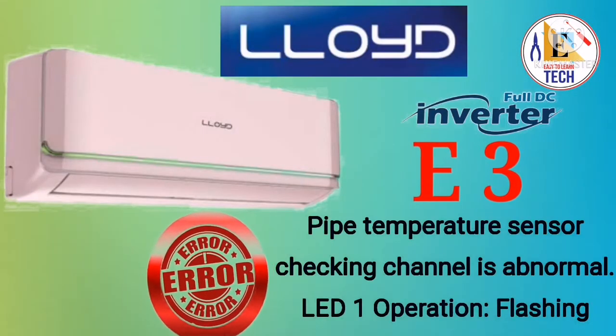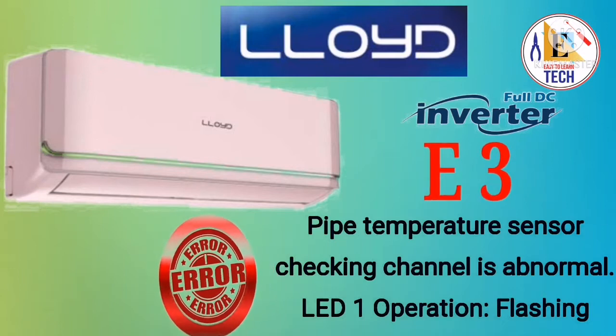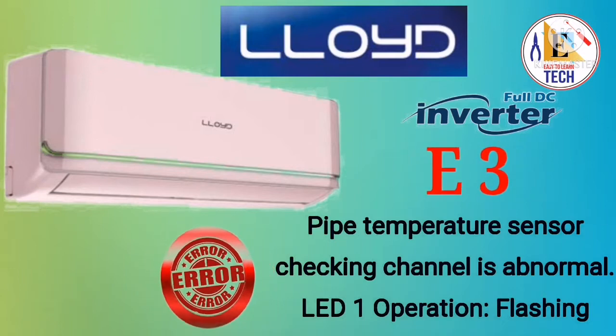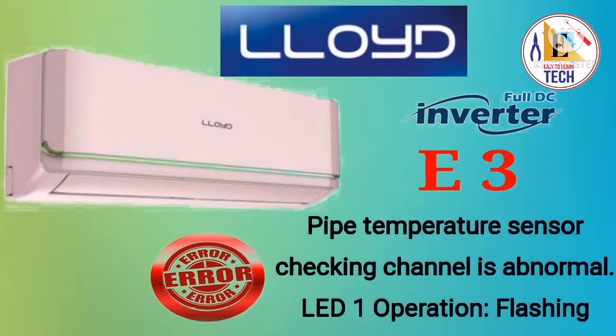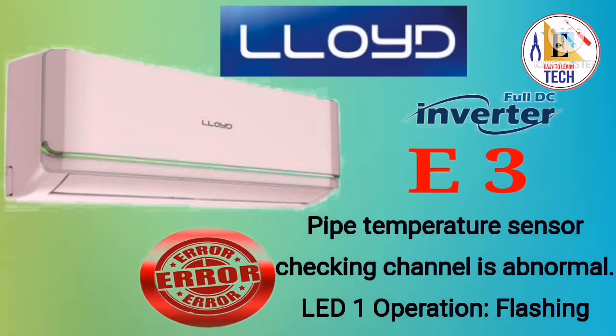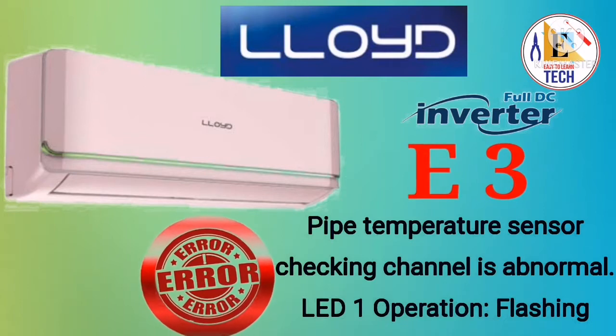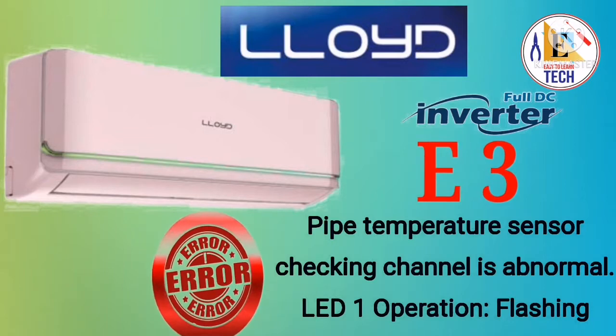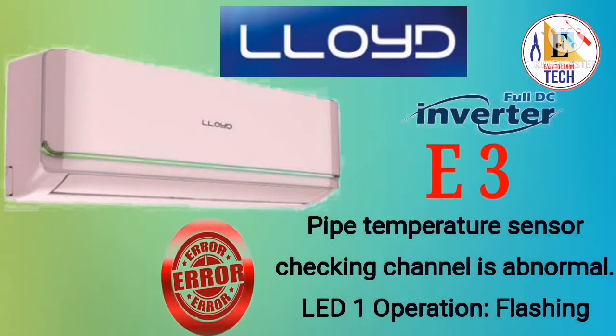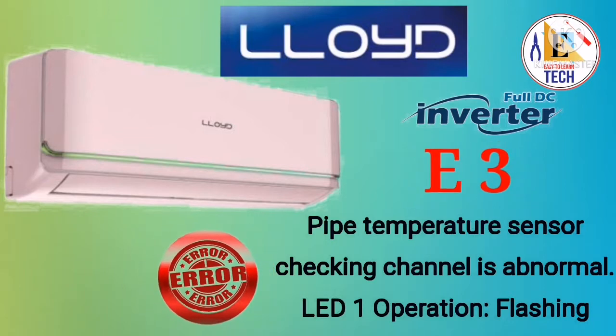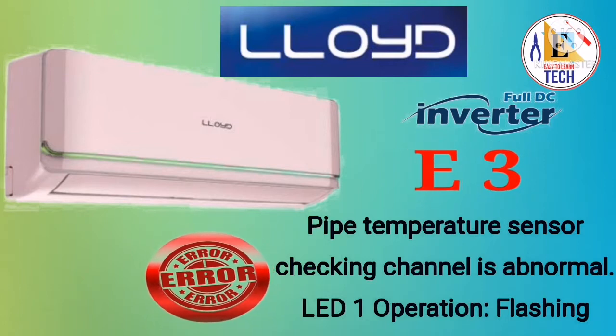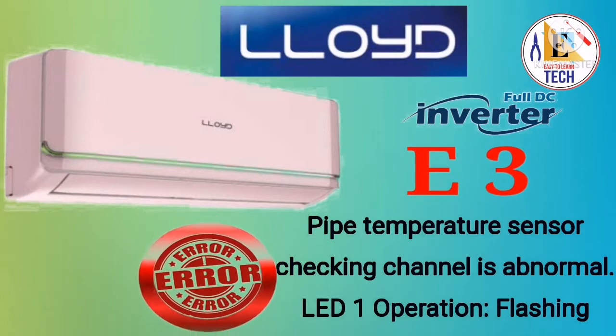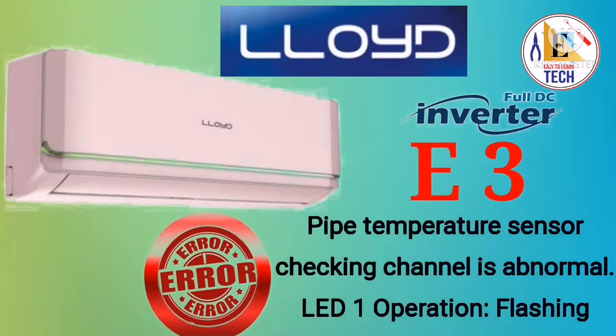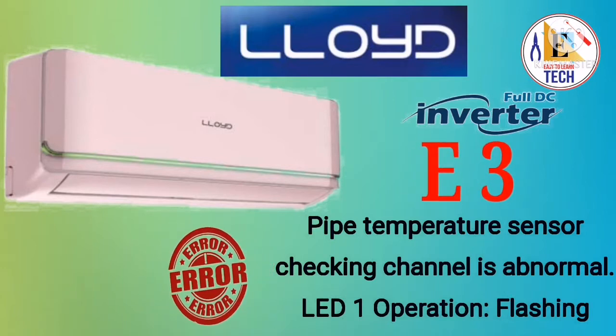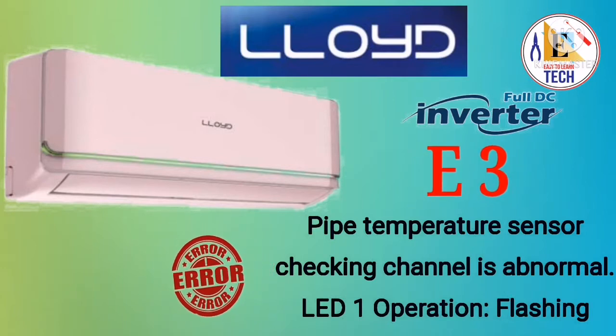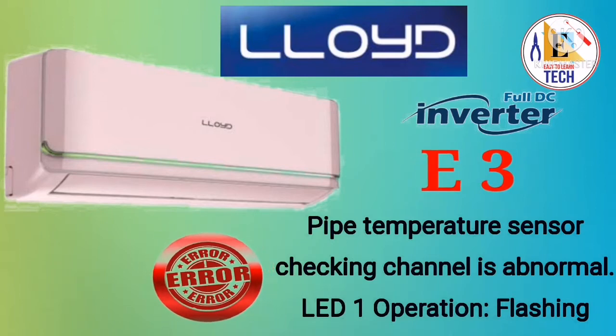When you see E3 in your display, or your LED1 operation is flashing, it means pipe temperature sensor faulty. It is called the pipe temperature sensor and it is also called the coil temperature sensor. In your indoor unit, near the coil, there is one sensor which is connected to the piping of your indoor unit evaporator. Then you have to check the connection in the PCB, whether the zip is connected properly, or check the wire between the sensor and the zip, if it is damaged or cut or not connected properly.